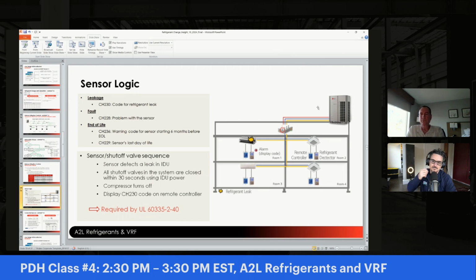So the way our system works is you're going to sense a possible leak at the indoor unit. That will then send a signal to all the shut-off valves to close. Your compressor shuts off, and I believe you then initiate the indoor unit fan on high speed to help dilute any refrigerant concentration in the room. And I want to mention that all of this is required per the UL standard. So we had to do this basically.